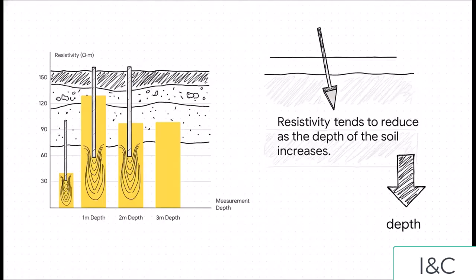Once you plot those averages, a really clear pattern starts to emerge. Near the surface, at 1 meter deep, the resistivity is up around 130 ohm meters. But as you go deeper, down to 2 or 3 meters, that value drops way down to under 100.